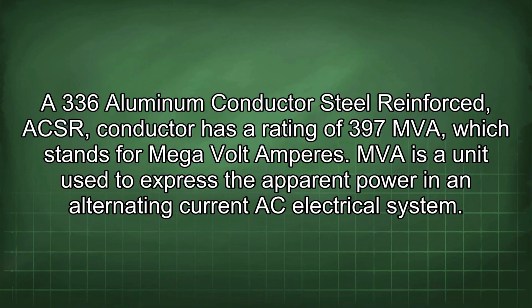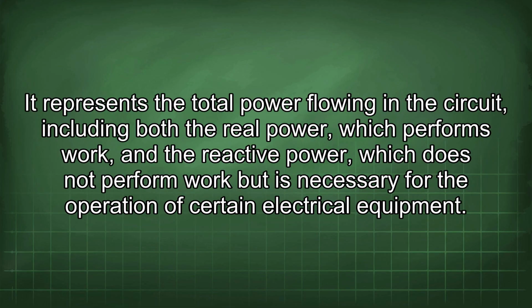A 336 aluminum conductor steel reinforced (ACSR) conductor has a rating of 397 MVA, which stands for megavolt amperes. MVA is a unit used to express the apparent power in an alternating current (AC) electrical system. It represents the total power flowing in the circuit, including both the real power, which performs work, and the reactive power, which does not perform work but is necessary for the operation of certain electrical equipment.